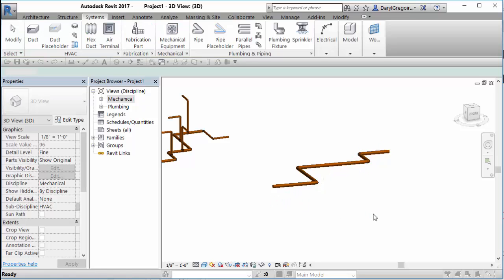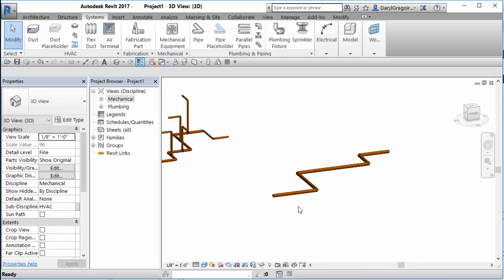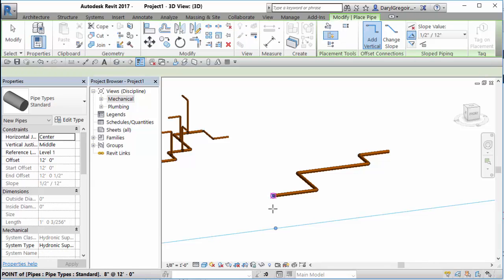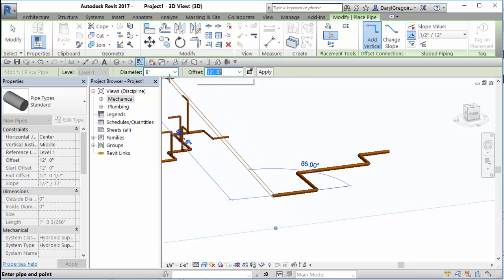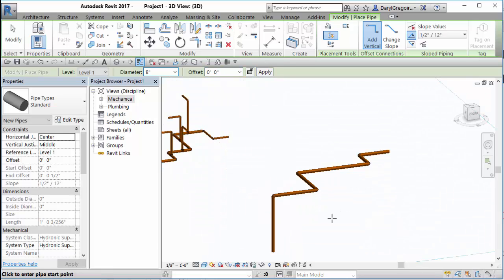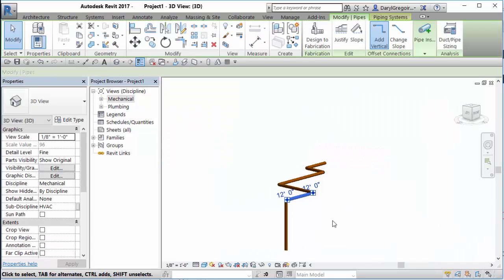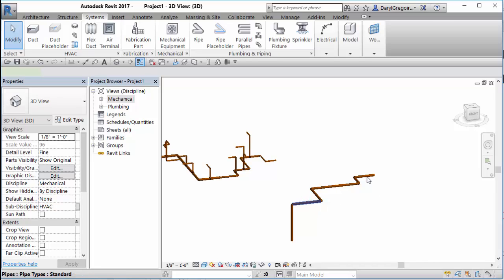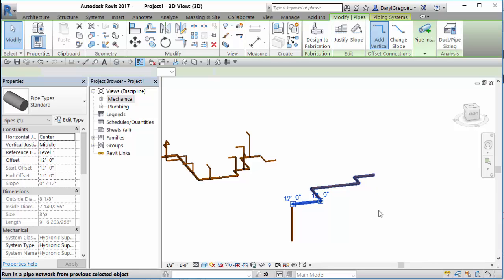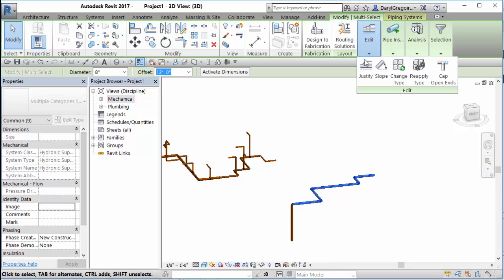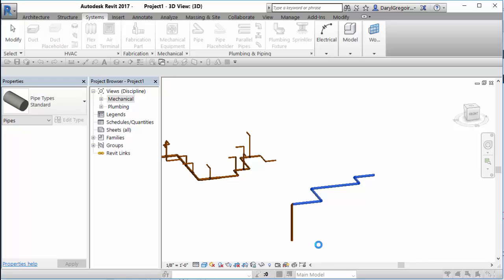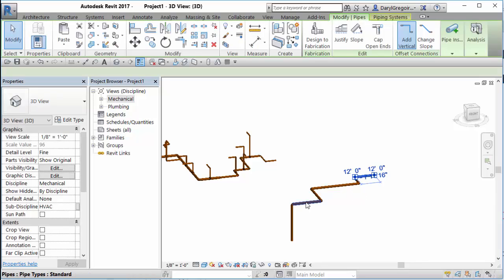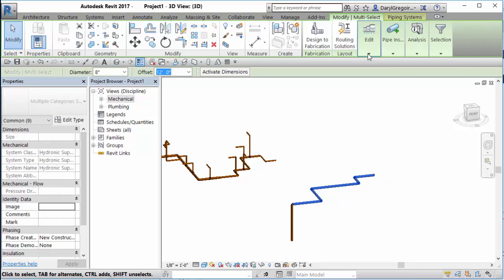If there is a vertical piece of pipe on the end, watch this: click on a pipe, say 'create similar,' hover over that end point, take an offset of zero feet, hit apply, and it draws a piece of vertical pipe. This pipe now knows there's a drain going straight down, and that makes a difference when we go to do our sloping.